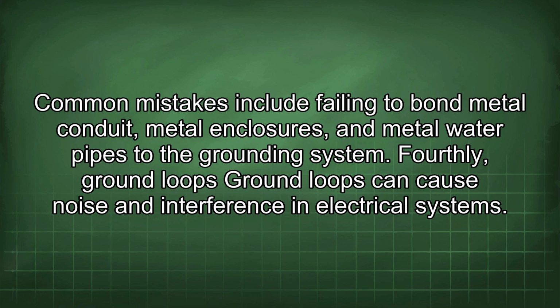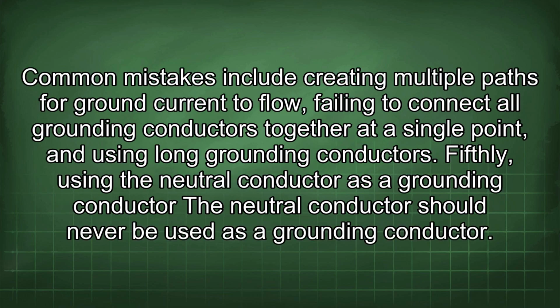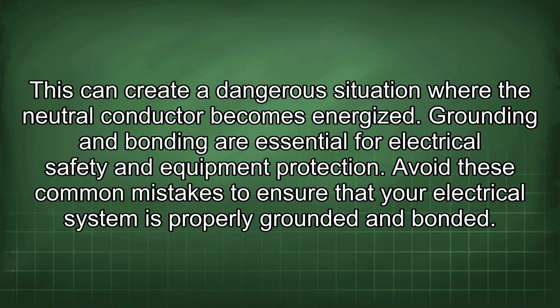Fourthly, ground loops. Ground loops can cause noise and interference in electrical systems. Common mistakes include creating multiple paths for ground current to flow, failing to connect all grounding conductors together at a single point, and using long grounding conductors. Fifthly, using the neutral conductor as a grounding conductor. The neutral conductor should never be used as a grounding conductor. This can create a dangerous situation where the neutral conductor becomes energized. Grounding and bonding are essential for electrical safety and equipment protection. Avoid these common mistakes to ensure that your electrical system is properly grounded and bonded.